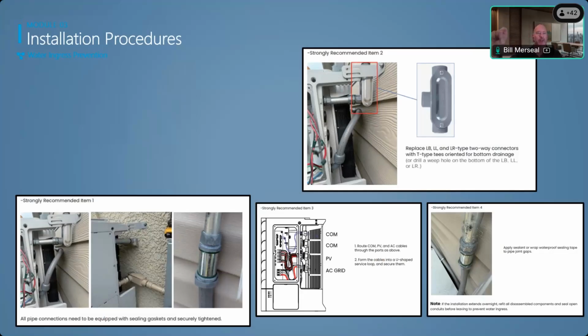What was happening was water was coming down the condensation lines, or basically they weren't sealed—the conduit wasn't sealed very tightly. So water would come in and go right into the box. Obviously when you've got your MPPTs and all your electronics in there, water coming in was really just creating havoc on the systems. We were shorting out our boards—all our stuff in there was getting shorted.